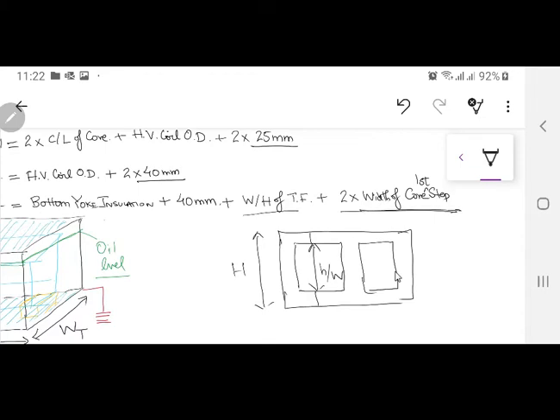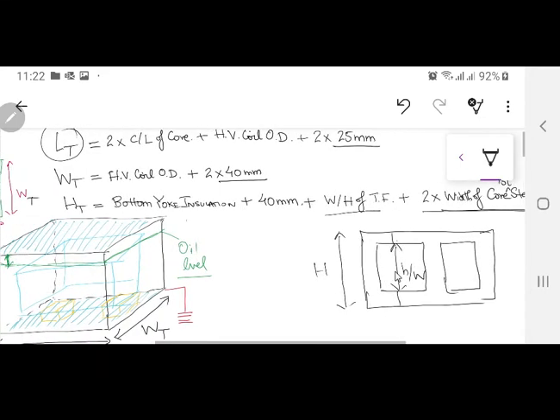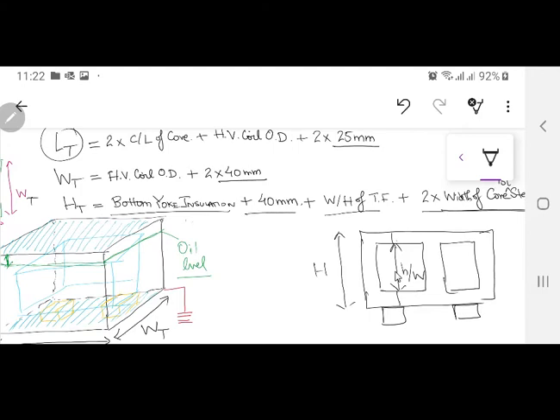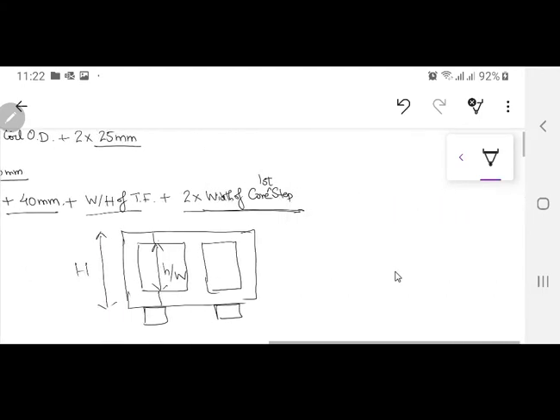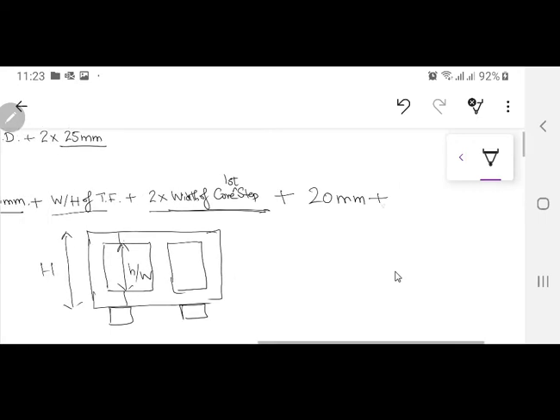Plus bottom yoke insulation, because you are going to put some wooden blocks underneath - 40 mm is the clearance added from the bottom. And then afterwards you add the next thing, which is again a 20 mm added over there. I will tell you why this is added, plus the tap changer height. The tap changer also has to come inside the tank, so it has to be there. And between the tap changer and the transformer there is going to be some clearance.